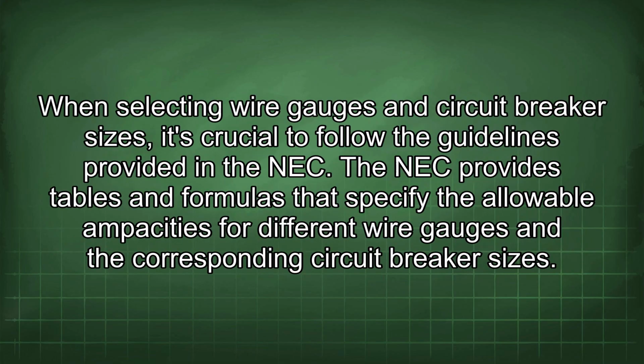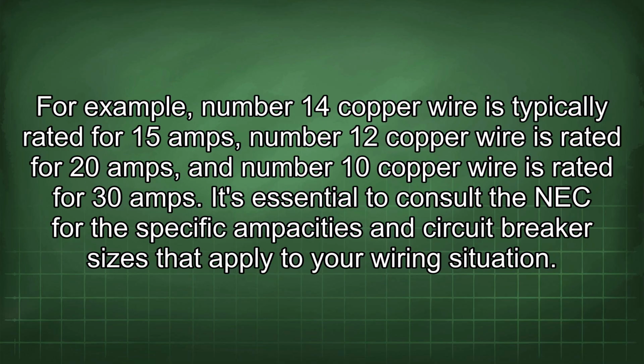When selecting wire gauges and circuit breaker sizes, it's crucial to follow the guidelines provided in the NEC. The NEC provides tables and formulas that specify the allowable ampacities for different wire gauges and the corresponding circuit breaker sizes. For example, number 14 copper wire is typically rated for 15 amps. Number 12 copper wire is rated for 20 amps, and number 10 copper wire is rated for 30 amps. It's essential to consult the NEC for the specific ampacities and circuit breaker sizes that apply to your wiring situation.